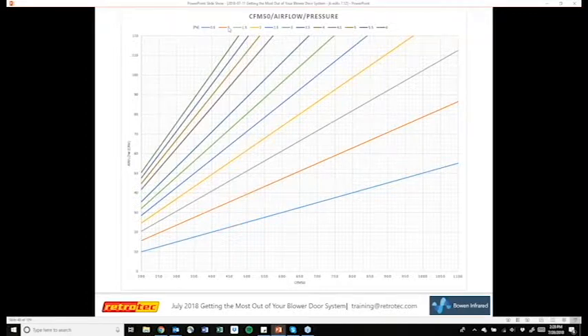Say you have a pressure difference of 1 and your blower door number is 1,000. So 1 is this orange line, 1,000 is here, and if we run it over to this y-axis, that's telling us our ventilation system is bringing in about 78 CFM. It's not a ResNet or BPI approved way of measuring ventilation, but it is a way to check and see if it is working if you can't really get to it.